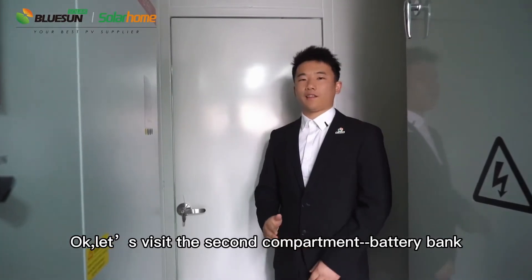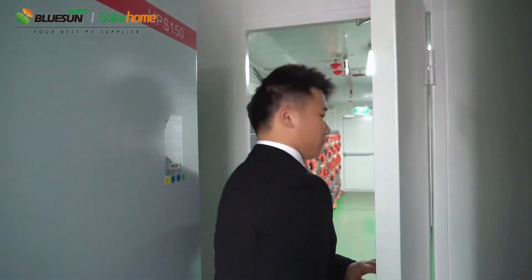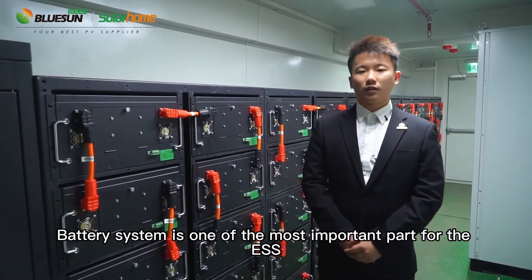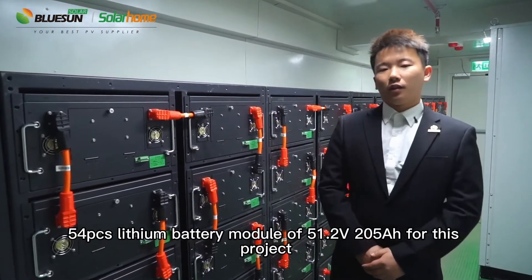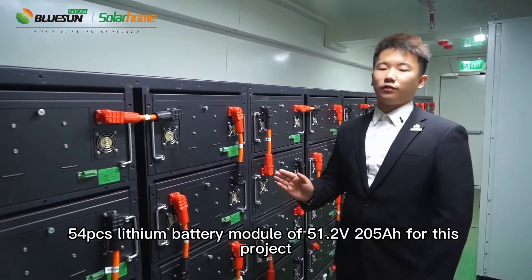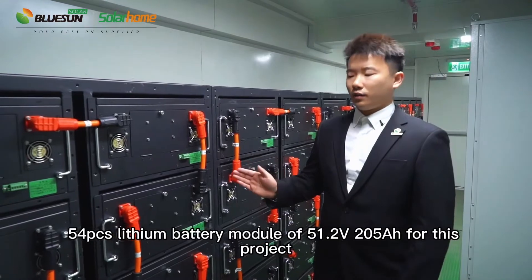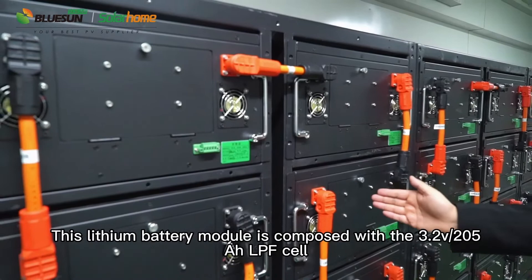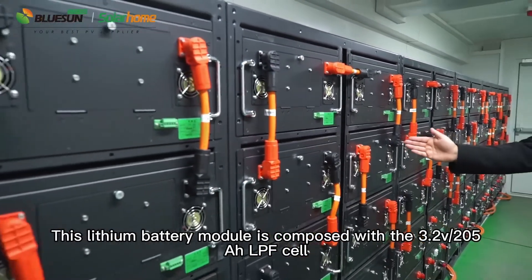Let's visit the second compartment — the battery bank. The battery system is one of the most important parts for the ESS. We have 54 pieces of the battery module at 51.2 volt, 205 ampere-hour for this project. This battery module is composed of 3.2 volt, 205 ampere-hour LFP cells.